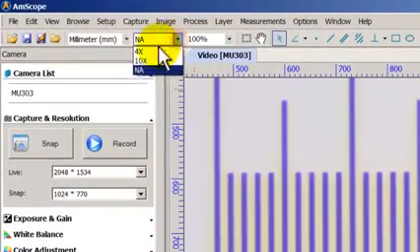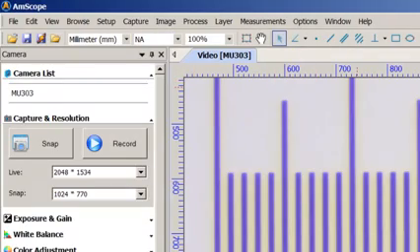Now what that did was it went ahead and saved the calibration for the 10x. So now I have both of the objectives, the 4 and the 10 from this microscope. Now it's saved permanently on my computer unless I decide to uninstall the program or delete it manually. So just to make sure that this is correct, let's go ahead and test it out again. The measurement layer is modified. Do you want to save changes? No, I don't want to do that.